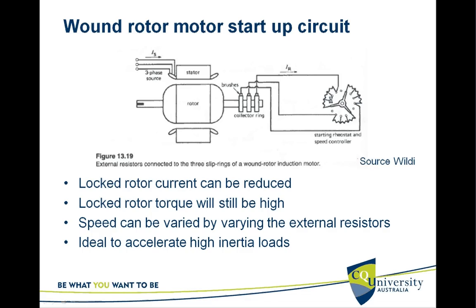You can increase or change the rotor resistance in all three windings in an equal manner, so that you do not affect the balanced loading condition in the rotor. The rotor will still be balanced.